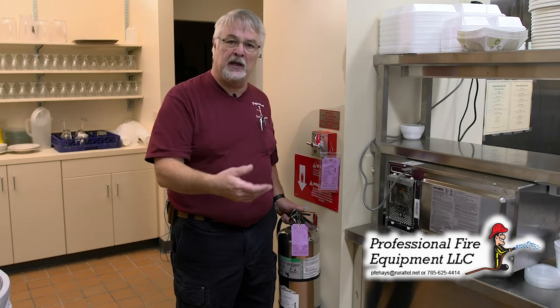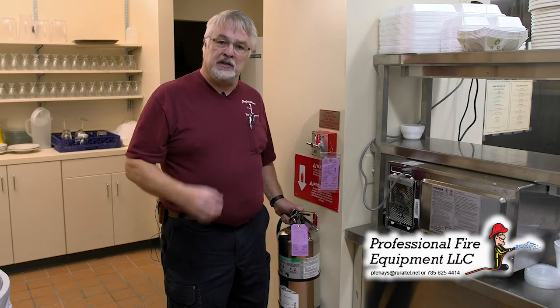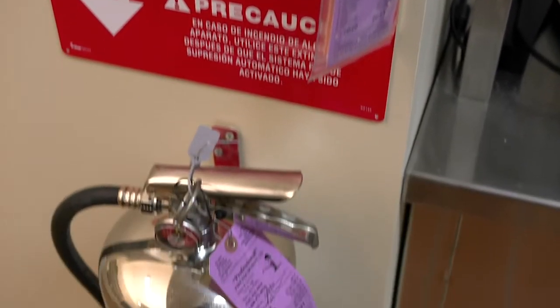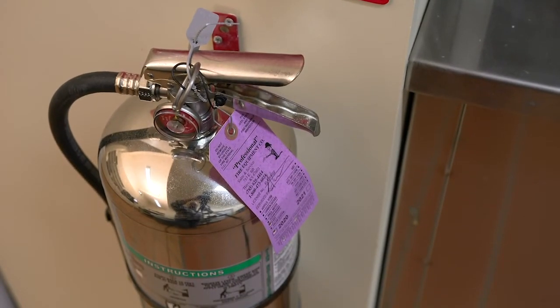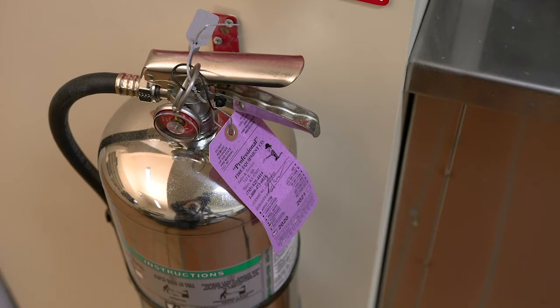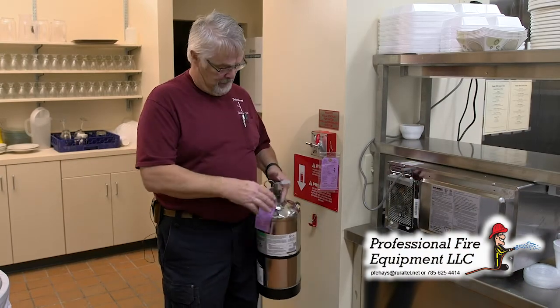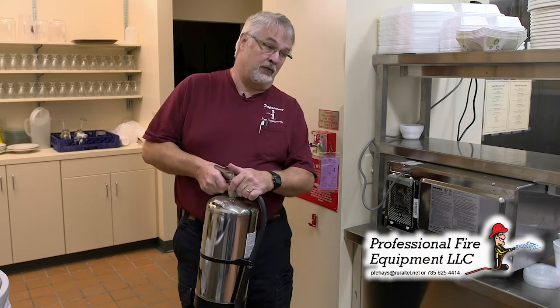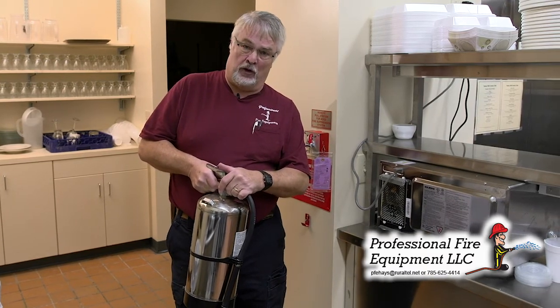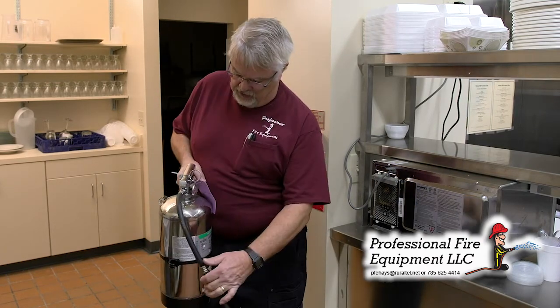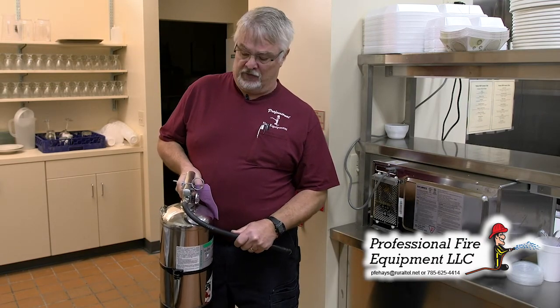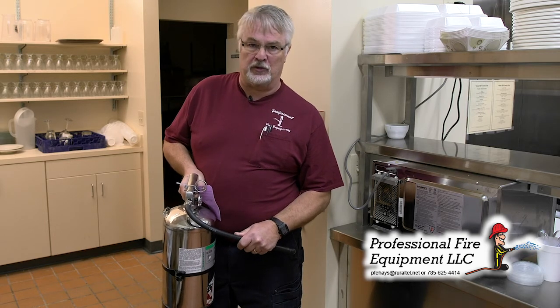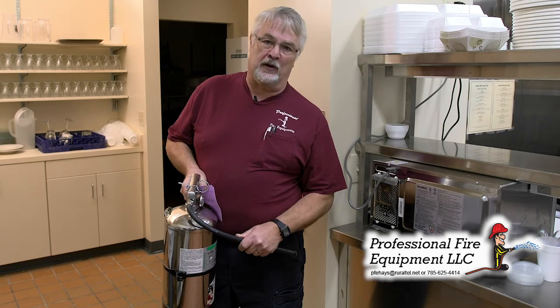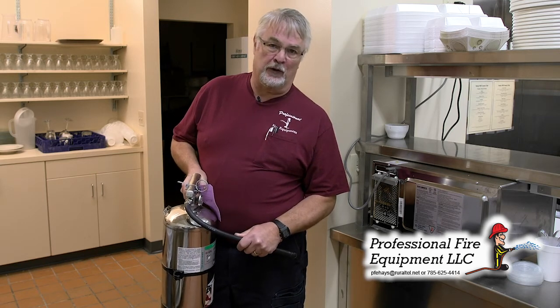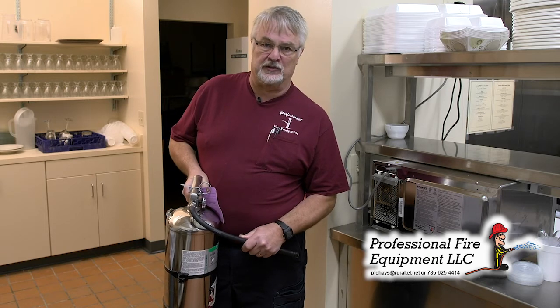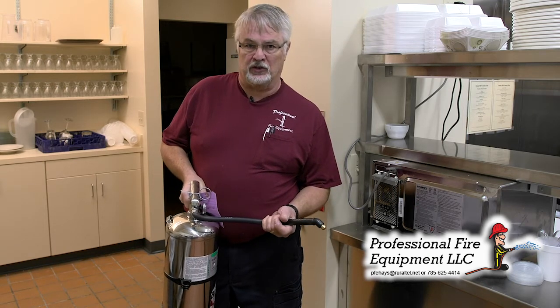From there, if it doesn't quite get it out, there might be grease down the backside of some equipment or something like that, we have what's called a K fire extinguisher. It's the same liquid that is inside the fire suppression system itself. So it will react with your grease the same way as your fire suppression system chemical will too. You want to use this after you've dumped the fire suppression system, after you've called 911. This fire extinguisher is meant solely for your kitchen. It's not the fire extinguisher you want to grab to go anywhere else in the building to put out a paper fire or to put out a car fire. It's more expensive to refill than a regular dry chemical fire extinguisher, but it is meant to put out the greases in the cooking process.